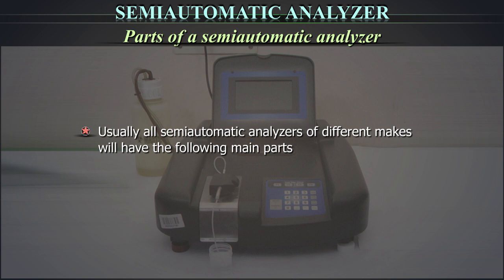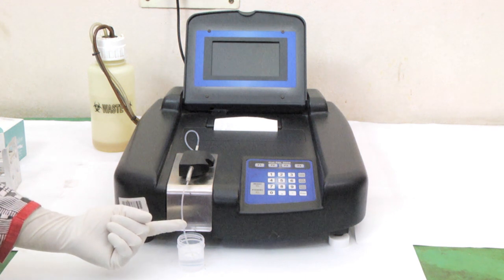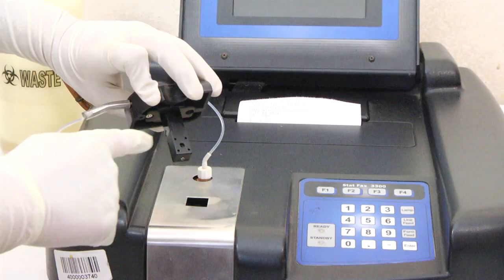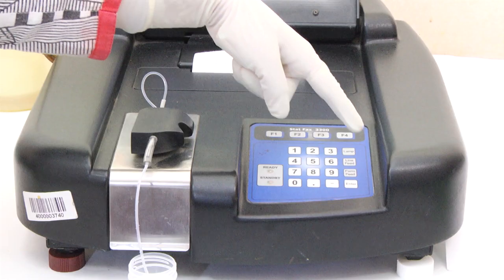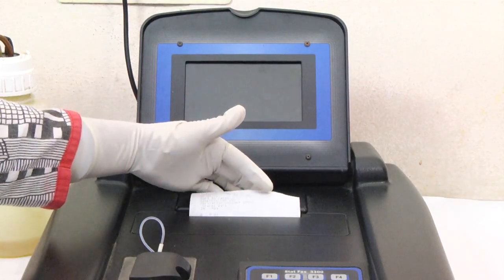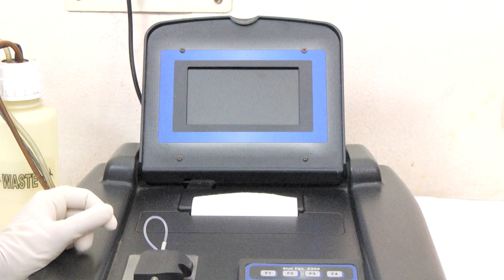Parts of a Semi-Automatic Analyzer: Usually all semi-automatic analyzers of different makes will have the following main parts: flow cell with aspiration tube. The flow cell has a tiny window through which the light passes. Screen, keypad with printer, waste bottle, and light source or lamp which is located internally.